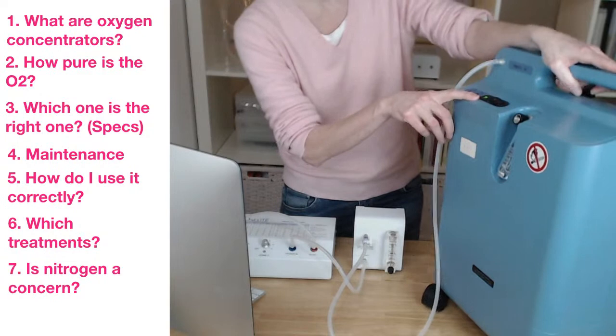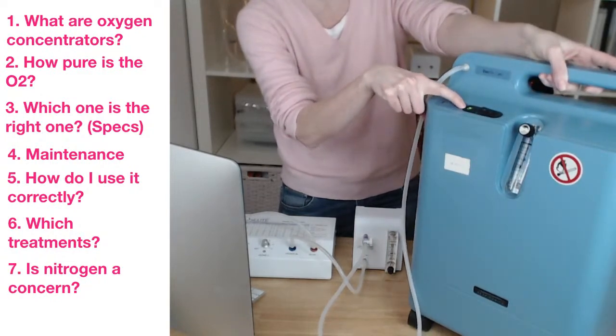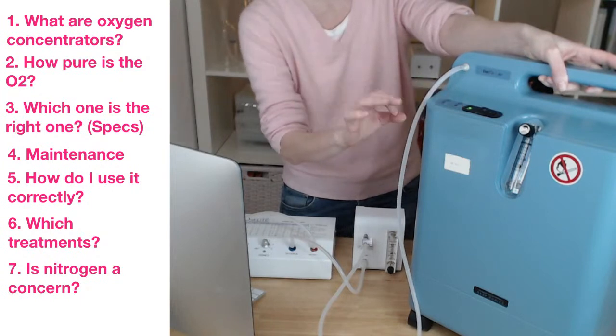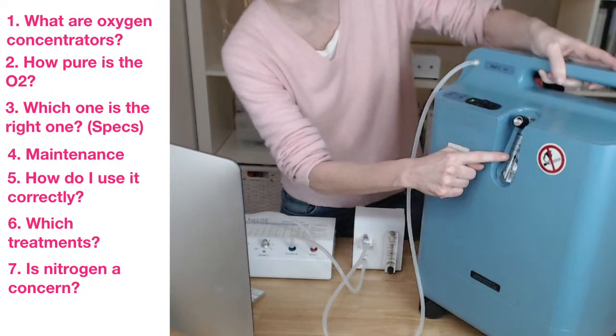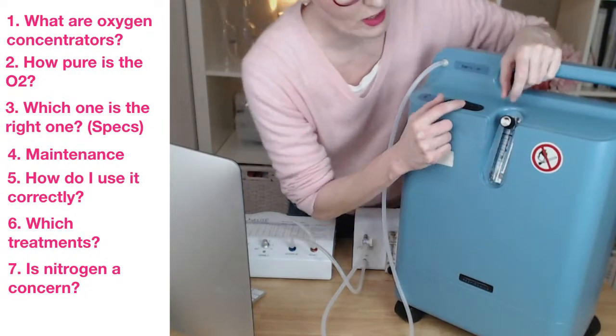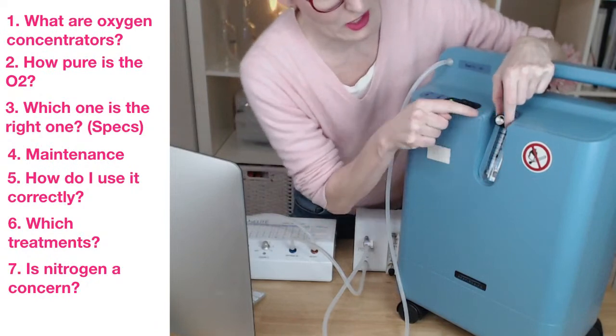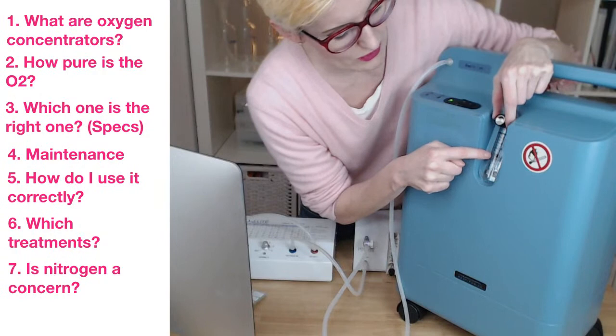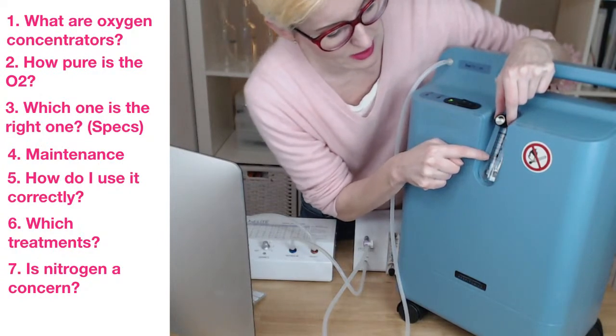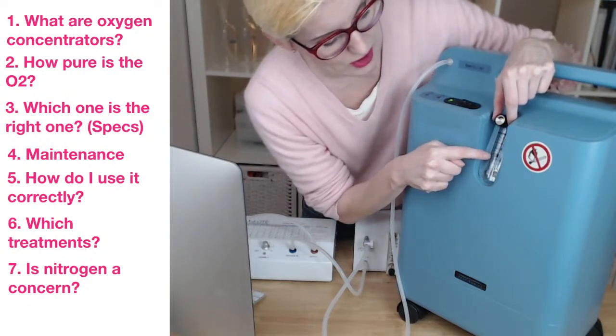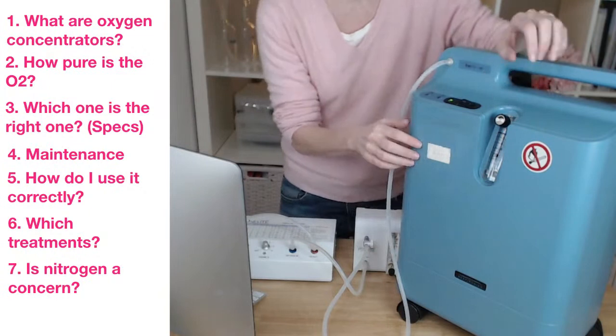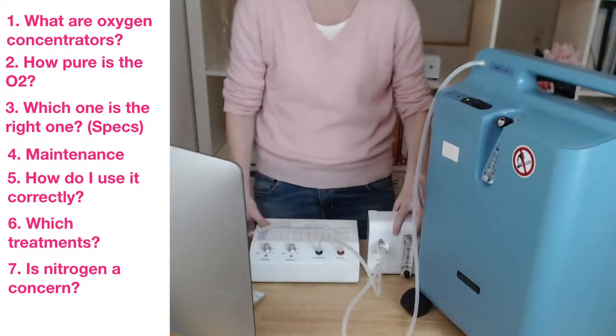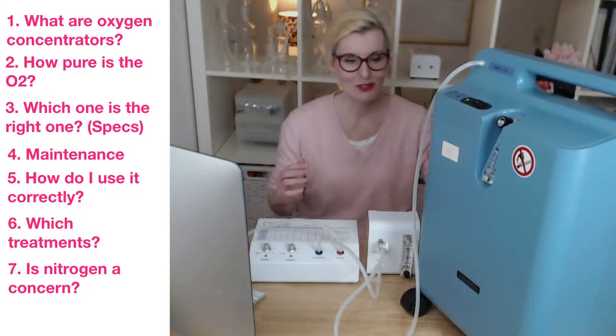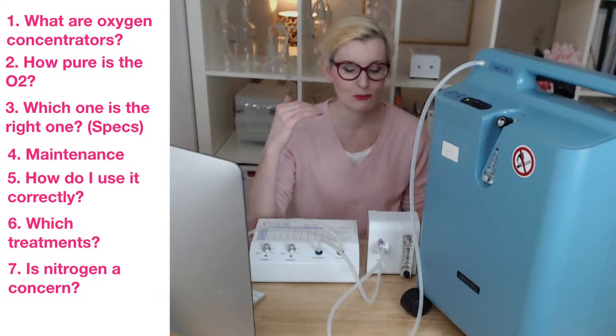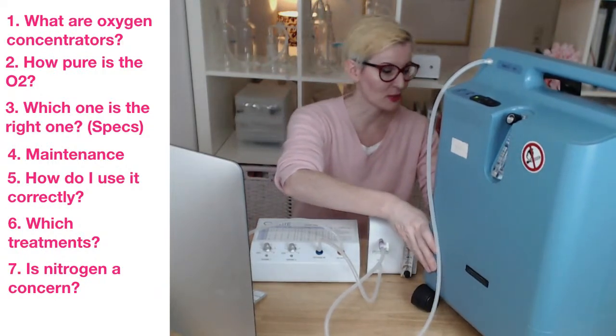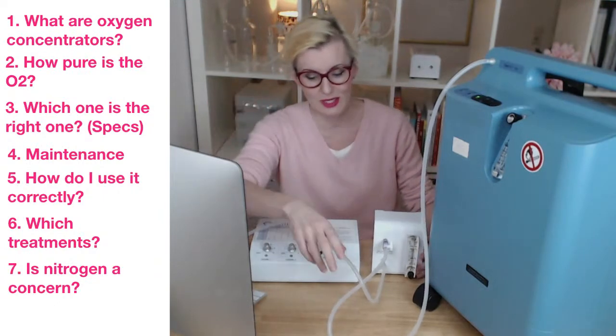When I turn the machine on, the green light should go on, and the green light tells me that everything is running fine. Then I take the built-in regulator, and here you see I can adjust the flow. I make sure that the black ball that shows me the setting, the level of oxygen, is at 2 liters per minute. Okay, and now if I was doing this properly, I should be waiting for 10 minutes for the machine to warm up, so that I'm sure it produces the maximum oxygen content that it can produce.